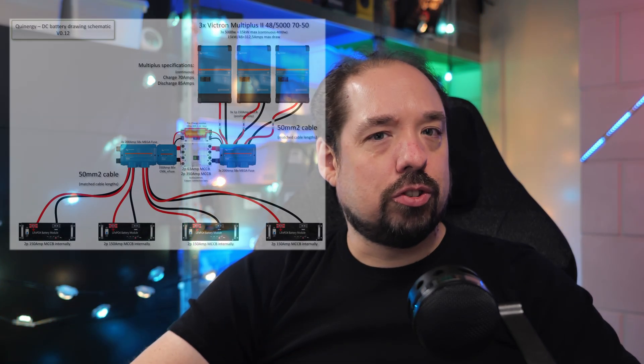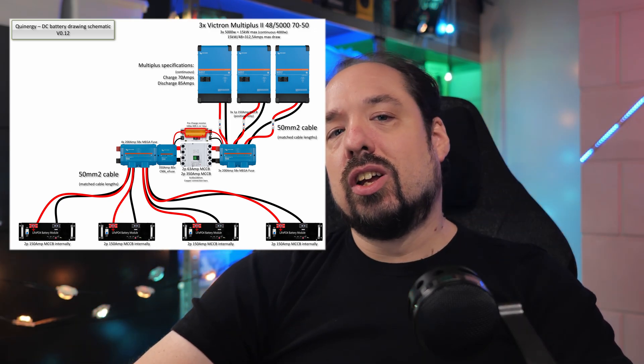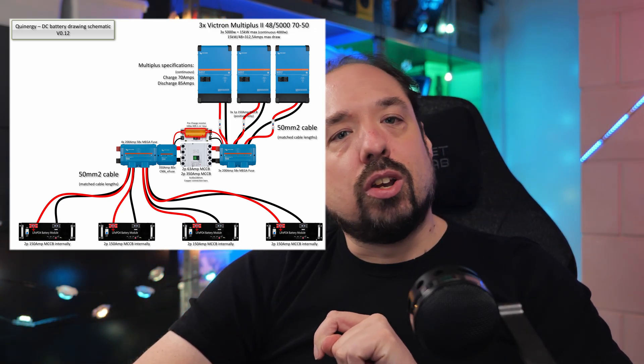As a last note, I wanted to highlight that on some of these places in this drawing, you'll see matched cable lengths. The reason for this is because a lot of this system is based on shared voltages between multiple pieces of equipment. In the end, all four battery boxes will end up working basically as a single giant battery. But to have this work correctly, it's important all their voltages are exactly the same. If one had a cable that is, say, one meter shorter than the others, the shunt, which just reads the generic voltage overall, would see that as its mark voltage and, for instance, stop charging when that one battery reaches the correct voltage while the others weren't quite there yet.